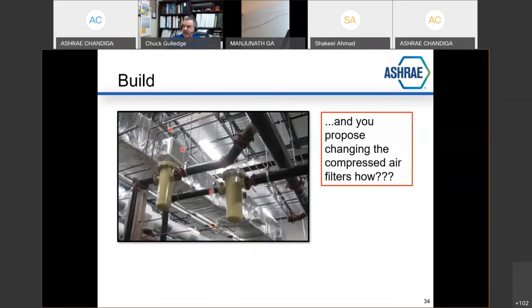And you propose changing the compressed air filters. How? Well, take a look at this. This is really nice ductwork, and this is nice looking compressed air piping. But look at the brilliance of this moment. These filter cartridge assemblies have to be removed off the top. This got located right underneath where a supply diffuser was on the trunk inside the mechanical room. How do you do that? How do you get away with doing that? It had to be redone.